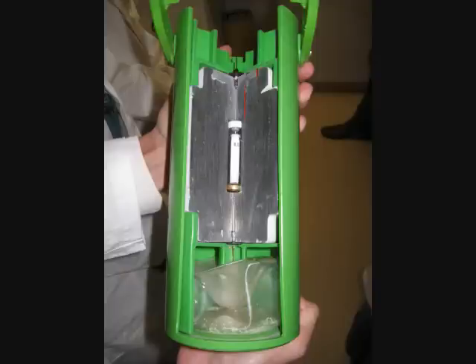You can see that the Molybdenum rod in the middle is shielded with lead, and on the bottom there is a little pouch that is usually filled with a sterile solution of sodium chloride. On the top — you can hardly see it — but there is a little needle. If you pierce that needle with an evacuated cylinder, you can simply suck up the sodium chloride from the bottom of the generator; it will flow through the chamber in the middle. The Molybdenum is chemically fixed to the rod, so very little of it comes off.